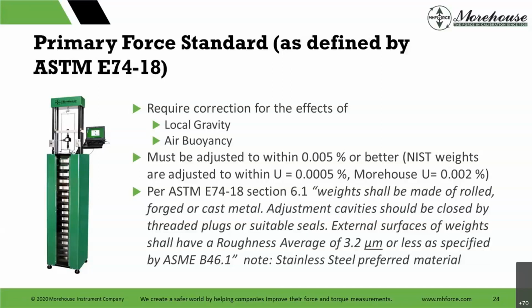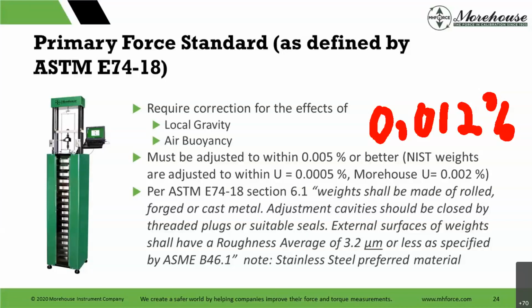Because air buoyancy, for those that do not know, is typically about 0.012%. That is usually the air buoyancy correction for force weights. You can adjust for gravity, for height, and some other things. And gravity varies all over the world, right? So if I have a weight that I'm sending to Alaska versus Florida, it's going to be different. Here in York, PA, when we adjust our weights for force, it takes 1,000.7 pounds of mass to equal 1,000 pounds of force when we do the correction for local gravity.